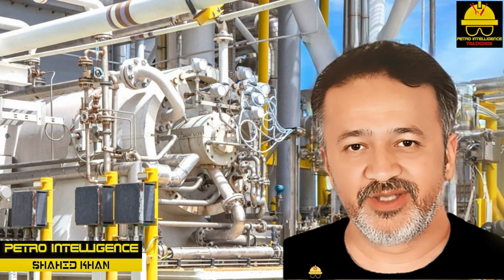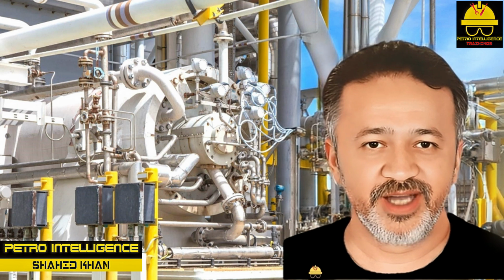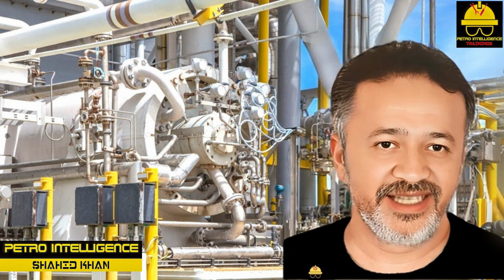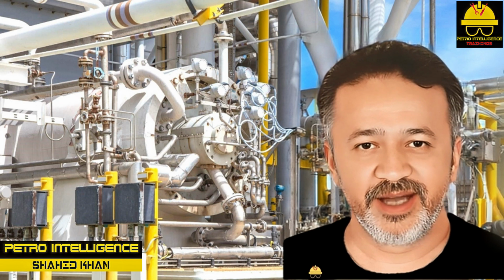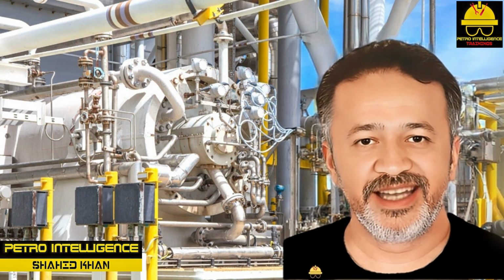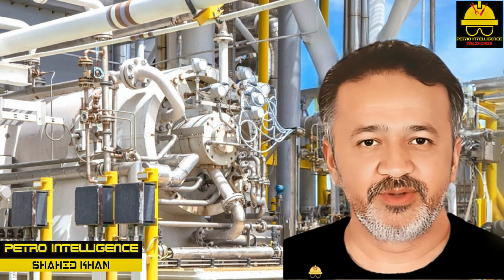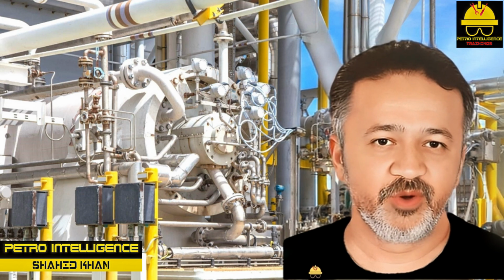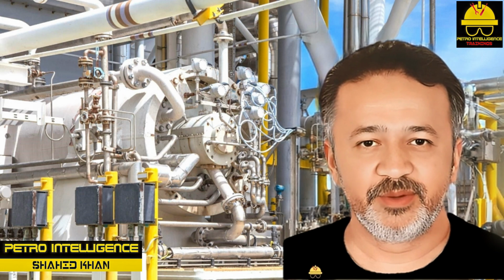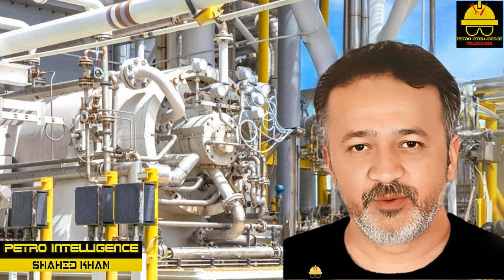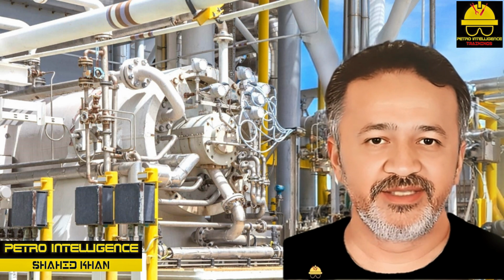The pressure at the discharge of each stage would be: first equals 47 psia, second equals 150.5 psia, third equals 481.7 psia, fourth equals 1,541.4 psia.